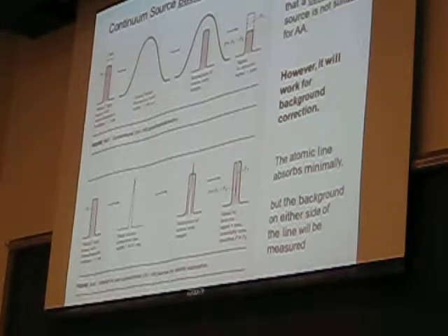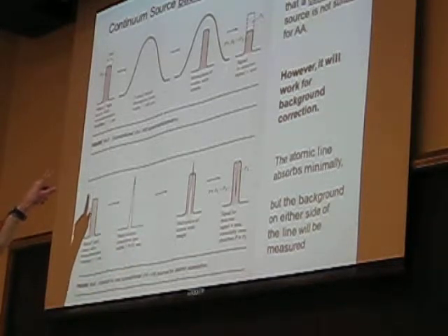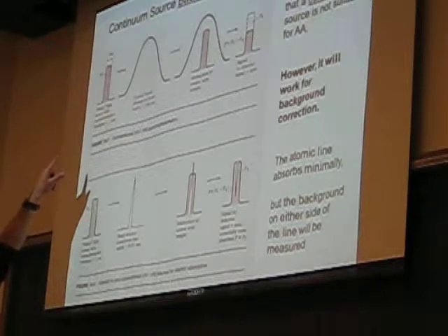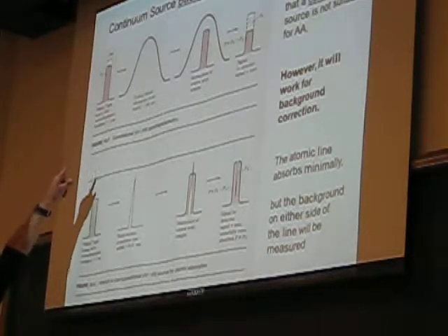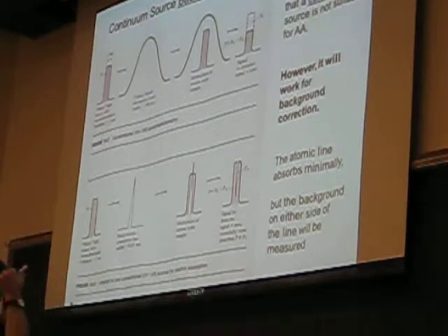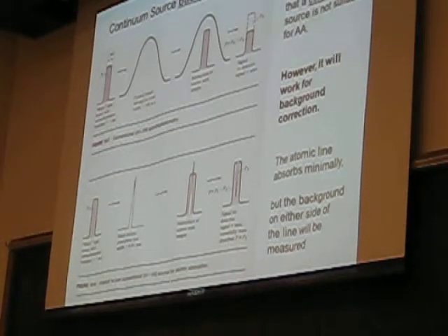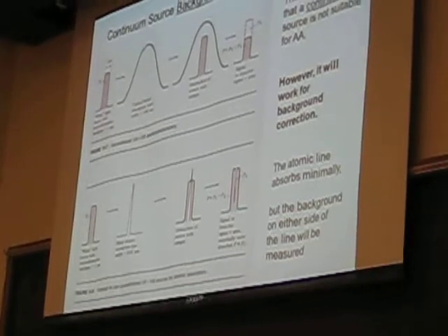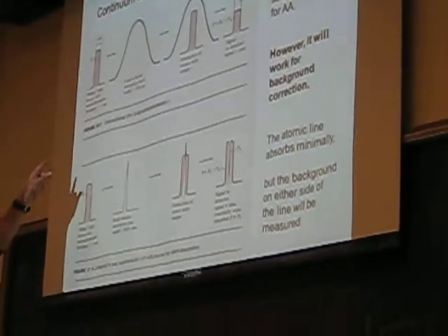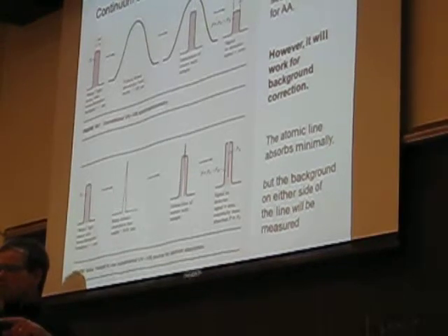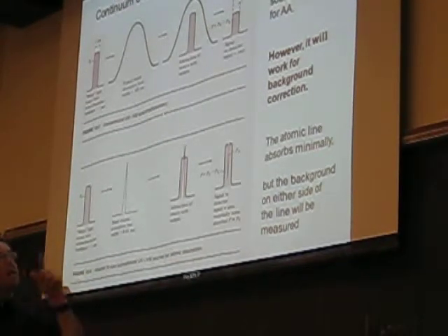And this is just meant to show that. So if you look at the top, this is normally what we were dealing with in UV-Vis spectroscopy. We generate light from our D2 lamp, and it has a relatively wide bandwidth of, say, a nanometer in this example. Right? And so you have a peak absorption maximum at 482, and we're able to select for light around 482 nanometers with a monochromator in UV-Vis. It's maybe 482 plus or minus a half a nanometer, right? So it's relatively broad. And then our molecular species is absorbing across a broad band. You do that wavelength scan, it looks like that.